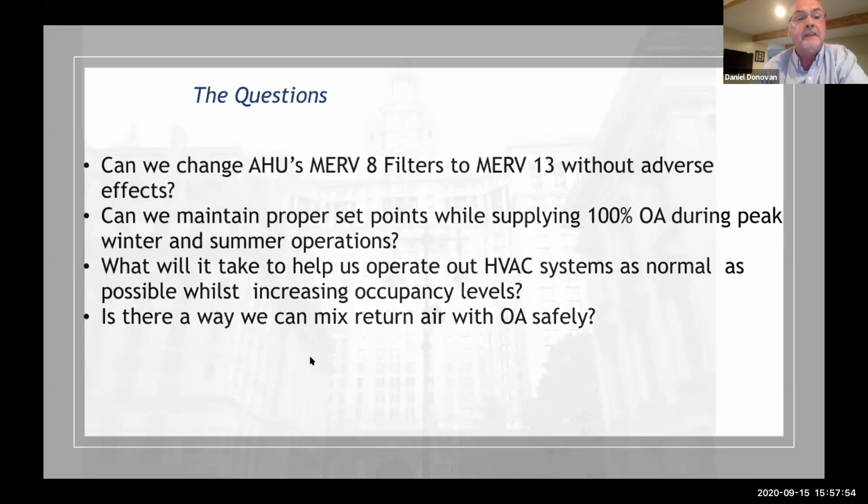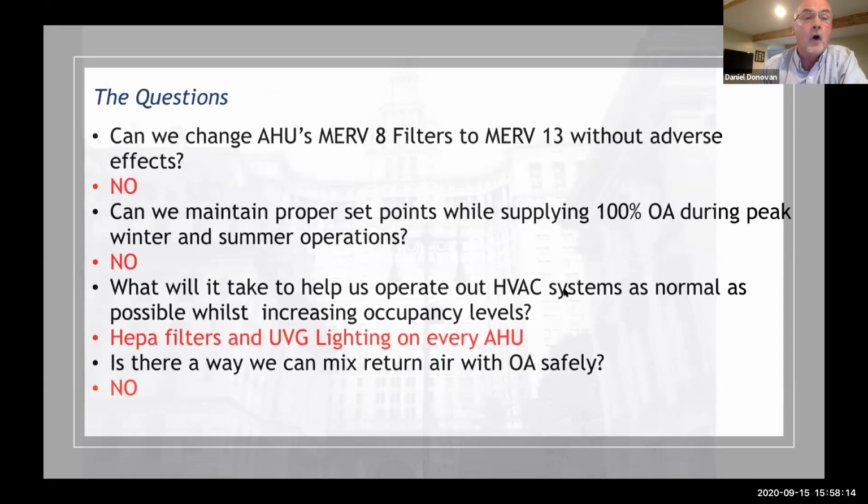Questions that have come up internally at the very beginning: can we change MERV 8 filters to MERV 13 without an adverse effect? All of the questions on this slide are typical of a lot of the questions that came up over time. And the answer to these is no, right? No to one, no to two. So what would it take to help us operate our HVAC systems as normally as possible while increasing occupancy levels? As Don pointed out, you're looking at HEPA filters, UVG lighting on every AHU.